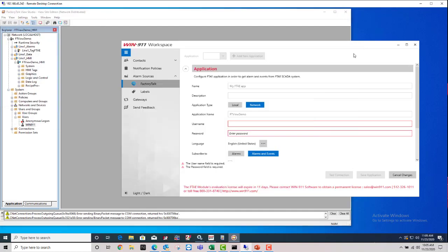So in the Factory Talk View Studio, you can expand Users and Groups and Users. And you can see I've made a Win911 user. And all you want to do is make sure you add it to the Administrators group as Membership. And password never expires.